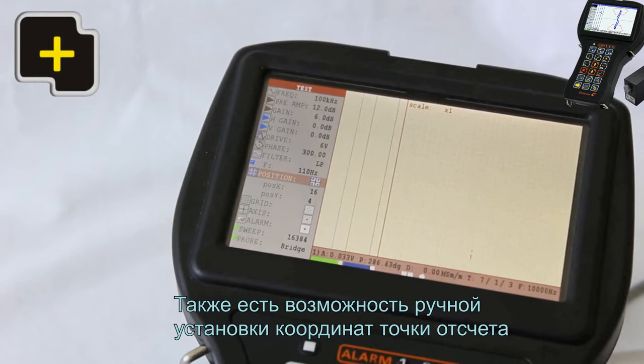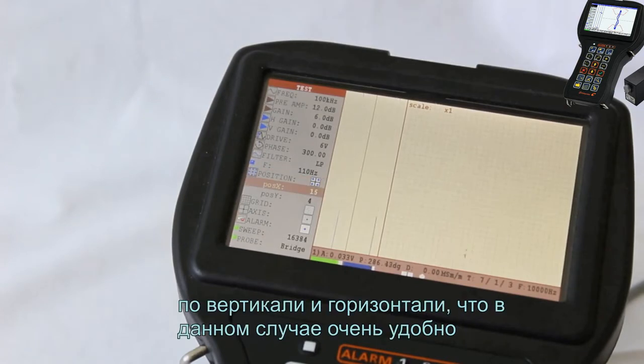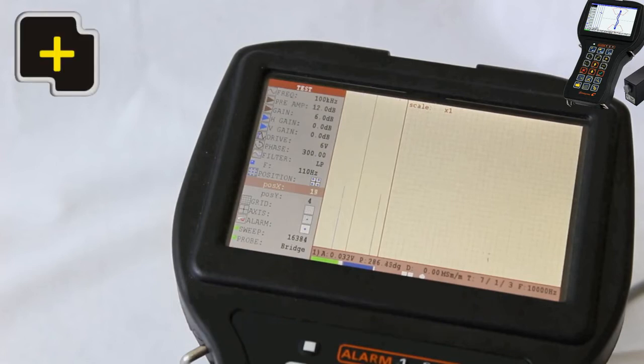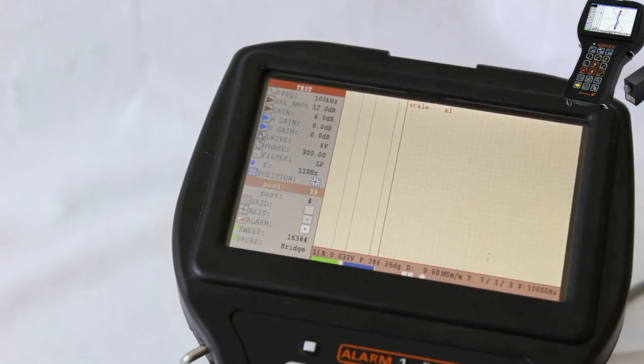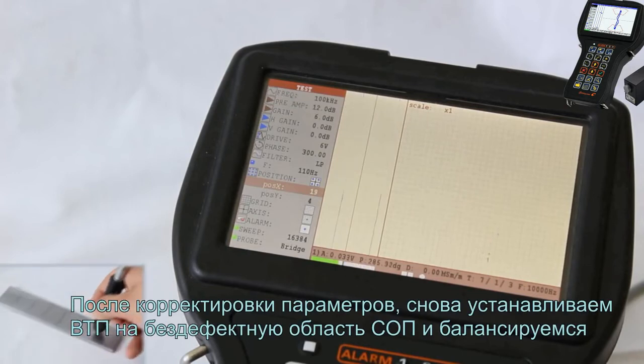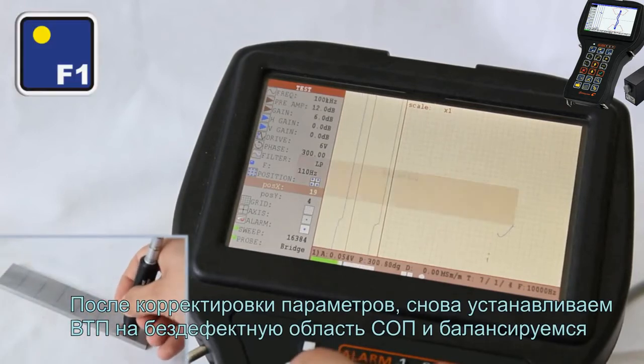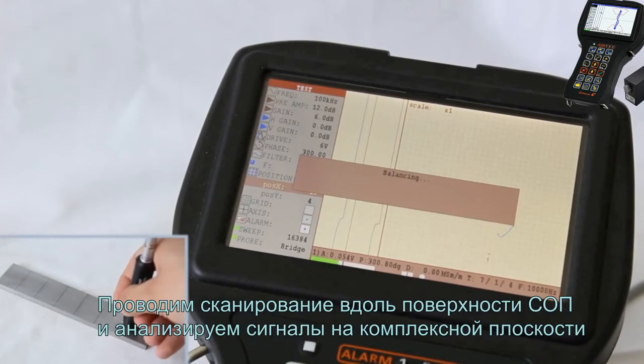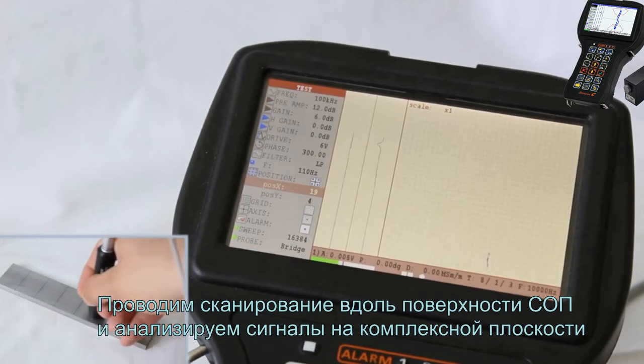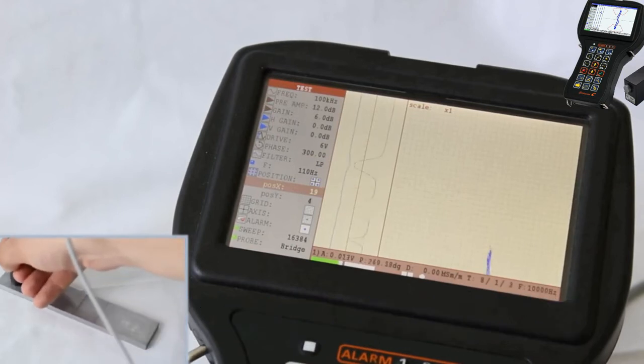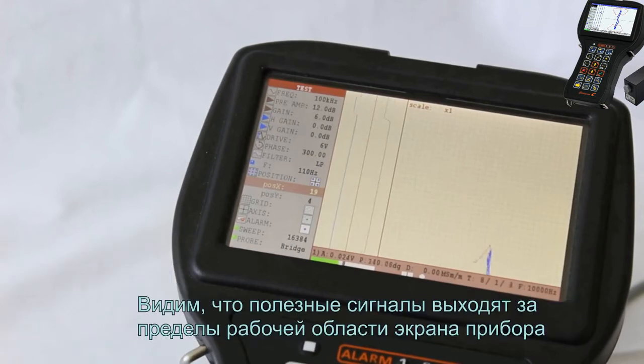Also, it is possible to set up manually the 0-point coordinates vertically and horizontally that is the most suitable in this case. After the parameters were corrected, once again place the EC probe at a flaw-free area of a block and perform the balancing. Carry out the scanning along the block surface and analyze the signals in a complex plane.